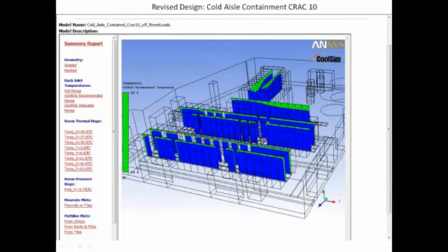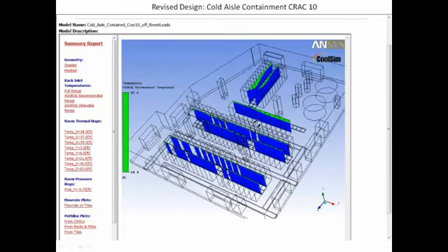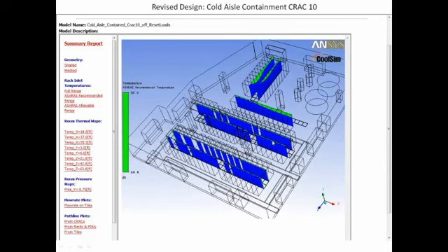But again, I would caution, even in the containment case, it's important to do the failure study to understand when I did containment, did it make my failure mode conditions better or worse? Because I have seen cases, Magnus, and maybe you have too, where you come up with this engineered solution to try to do containment or try to manage your airflow, and you study it in the failure mode, and it's actually worse than it was before.